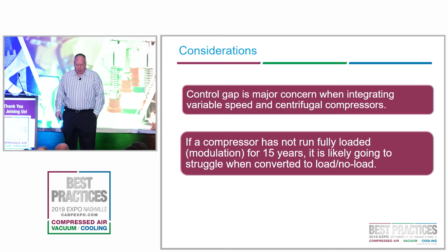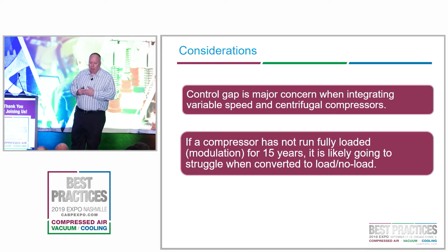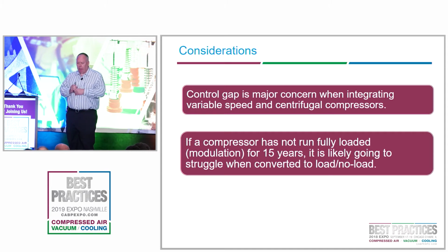But you have to be smart about it, especially with multiple variable speed or multiple centrifugal compressors. Turn down on a variable speed compressor is far greater than turn down on a centrifugal compressor. So depending on the number of compressors and how your air usage varies over the day or week, that needs to be considered, because it's common to have a system that works beautifully on first shift but is completely out of control on second and third shift, since that wasn't the focus of the design. It was designed to handle peak conditions but doesn't handle off-load conditions as well.